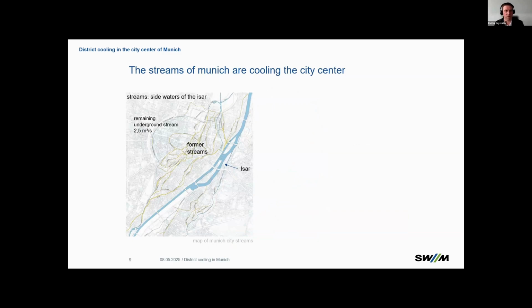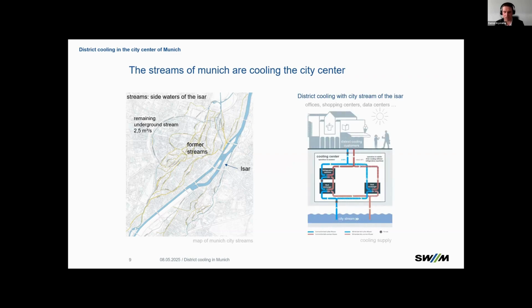As I said before, we are using the streams in Munich. Mainly it's from the Isar, and there are remaining underground streams with the water from the Isar, and we use it to recool, which is mainly for the efficiency. So we take out the water and transport it to the plants where there's a chiller, a refrigerant machine that is doing the recooling, or in the winter time we use a heat exchanger to make direct cooling, which is very efficient. As you can see, the whole system is very efficient.